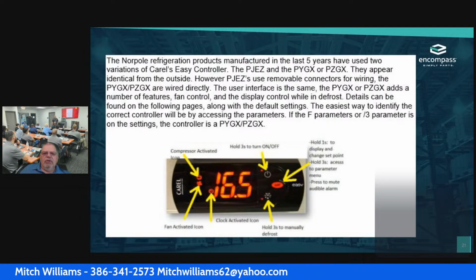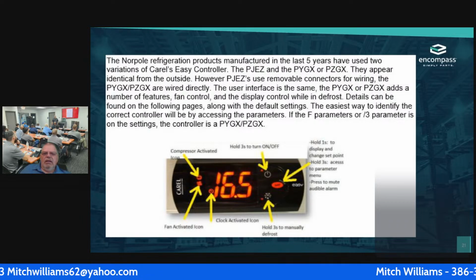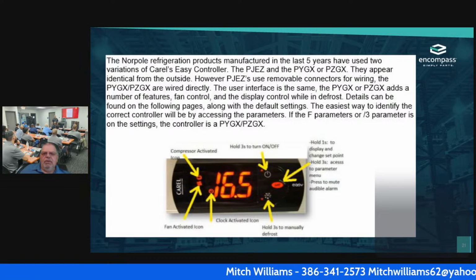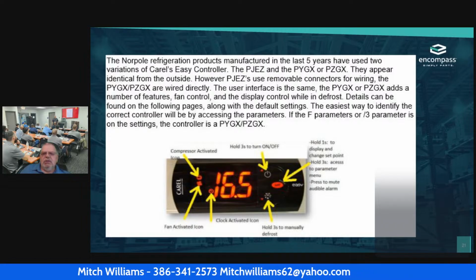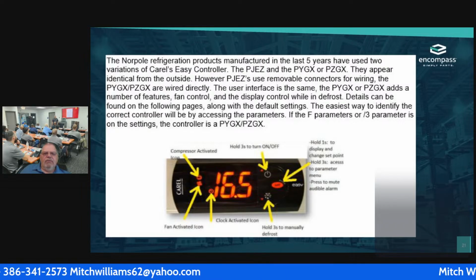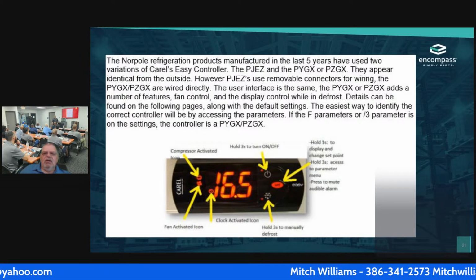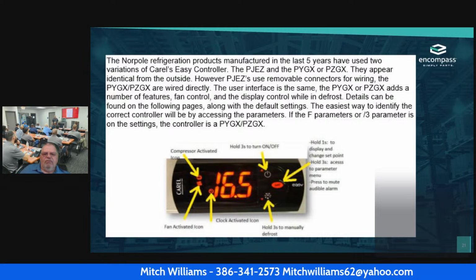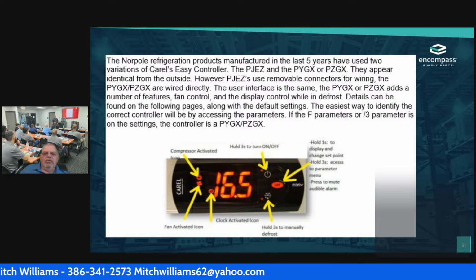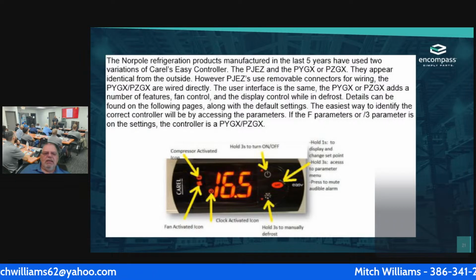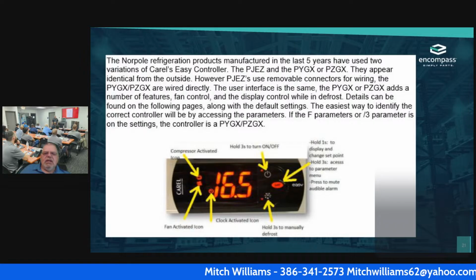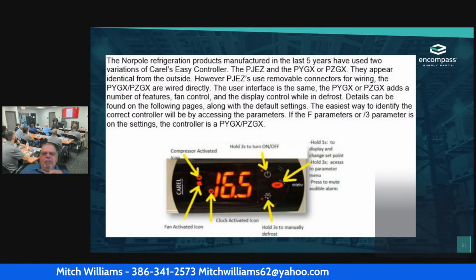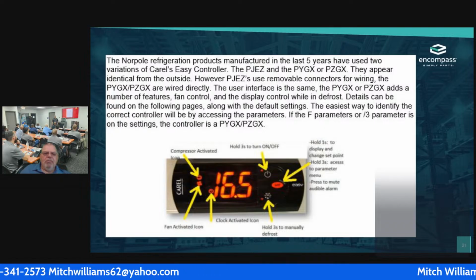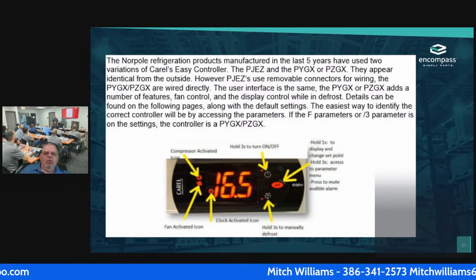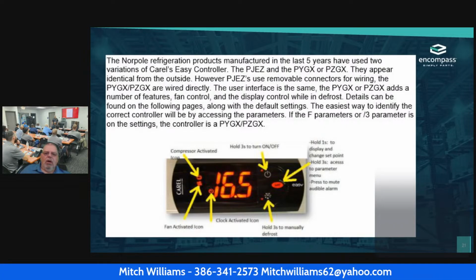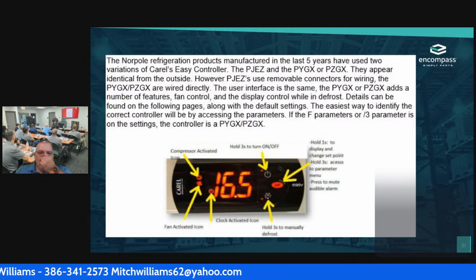Okay, the user interface is the same on any of them. The PYGX and the PZGX add a number of features, the fan control and the display control while in defrost. The details can be found on the following pages that we're going to go through, along with the default settings. So the easiest way to identify the correct controller will be by accessing the parameters. If the F parameters or the /3 parameter is in the settings, the controller is a PYGX or a PZGX. Okay, so that's how you tell.